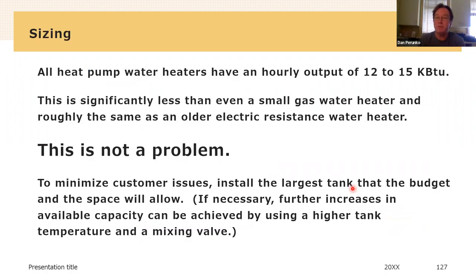All of these machines, including the Sanden, have a low heating output, right? So I've put in gas water heaters over the years that can do like 100,000 BTUs per hour. So you can heat like the whole tank of water, 50 or 60 gallons, in like 15 minutes. These heat pump machines take hours to heat their 50 or 60 gallon tank. And it's generally not a problem, right?